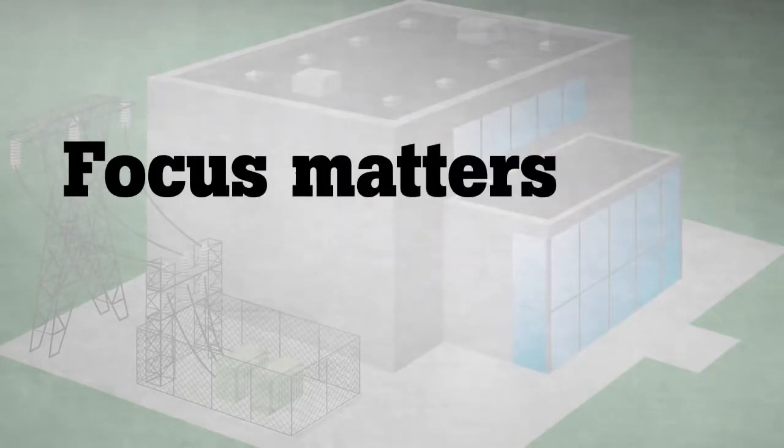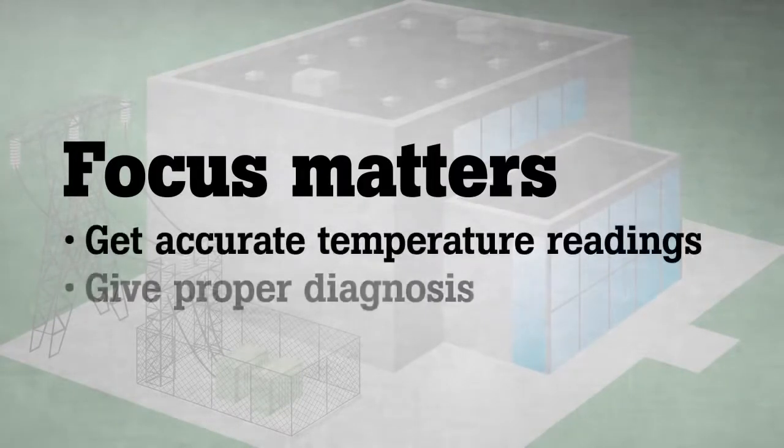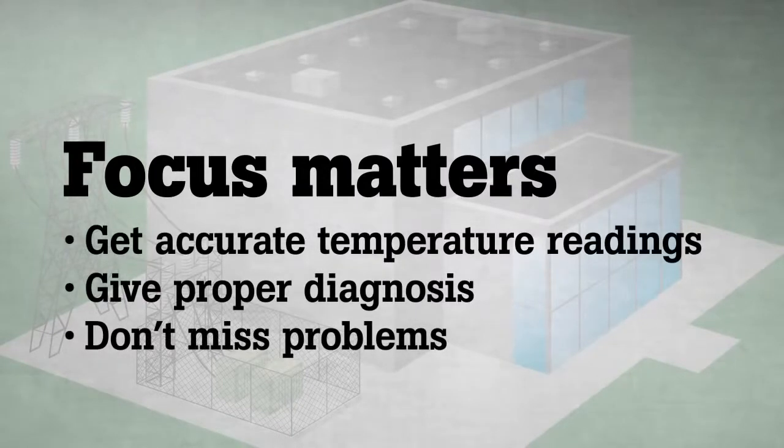Every infrared camera user knows that focus is the single most important thing to ensure when conducting an infrared inspection. Without an in-focus image, temperature measurements are often not as accurate—sometimes by as much as 20 degrees—and out-of-focus images make it much easier to miss a problem.